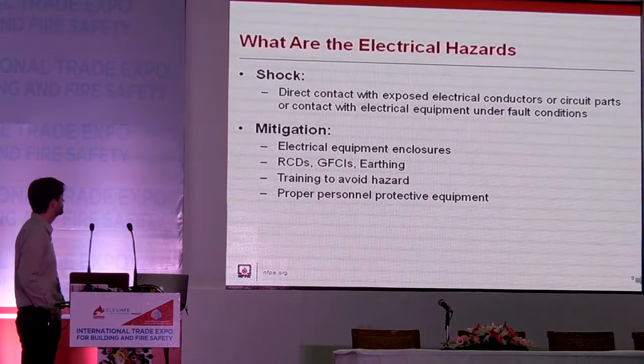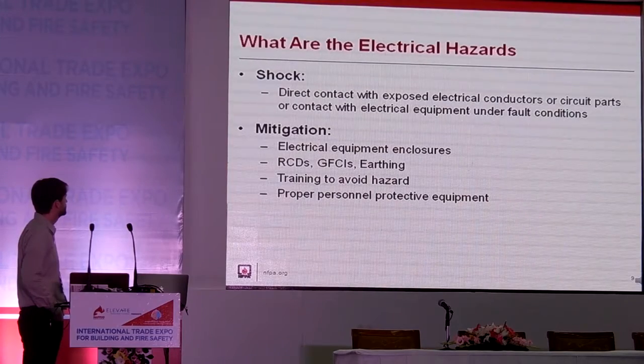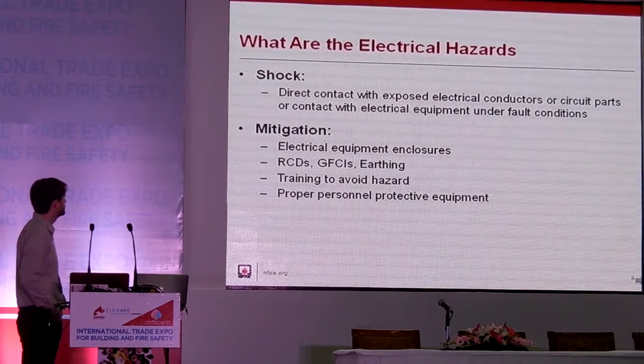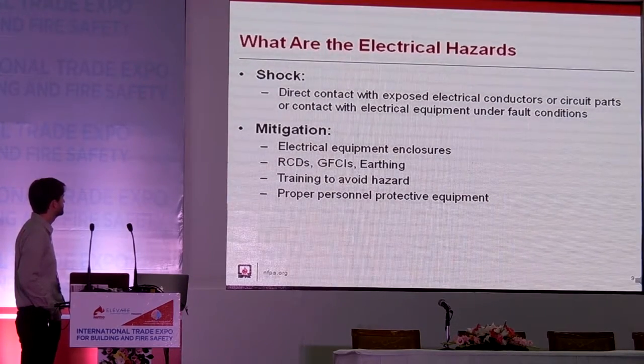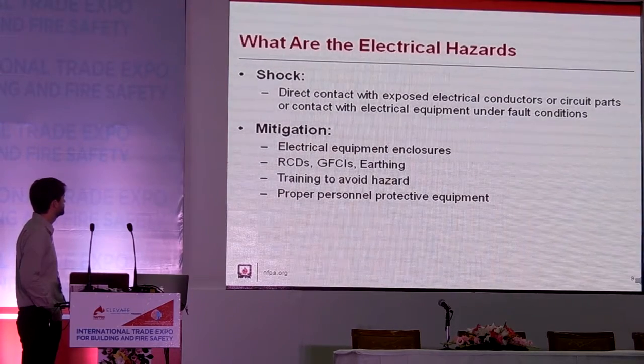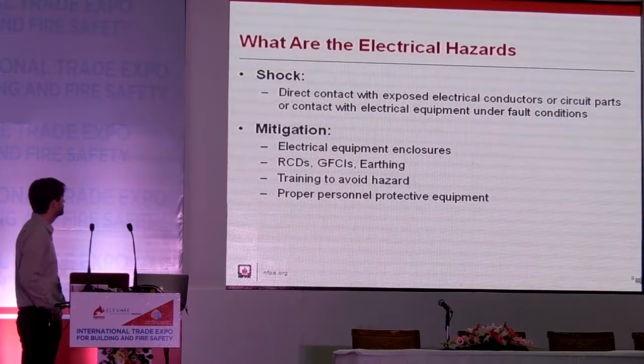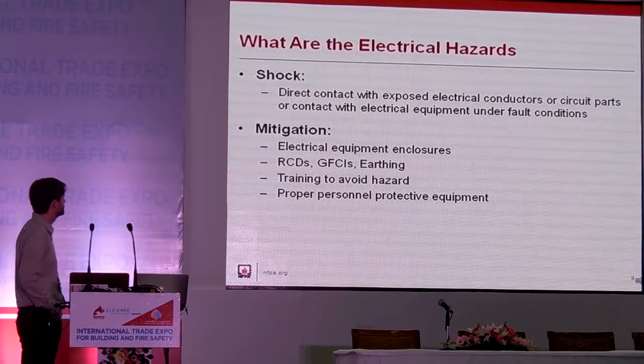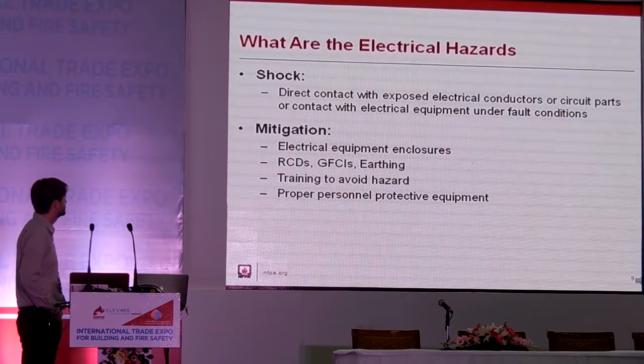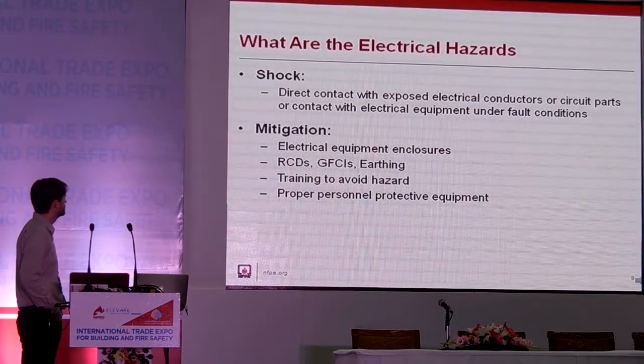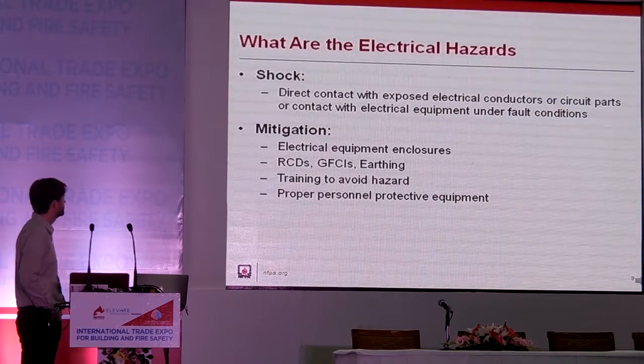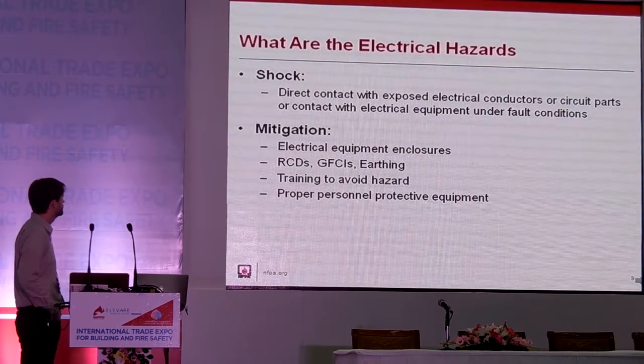An electric shock can result from direct contact with energized conductors or circuit parts, such as a maintenance person might encounter when they open up an electrical equipment enclosure, or a shock hazard can result from electrical insulation failure that energizes the surface of equipment that is normally not intended to be a current-carrying surface.